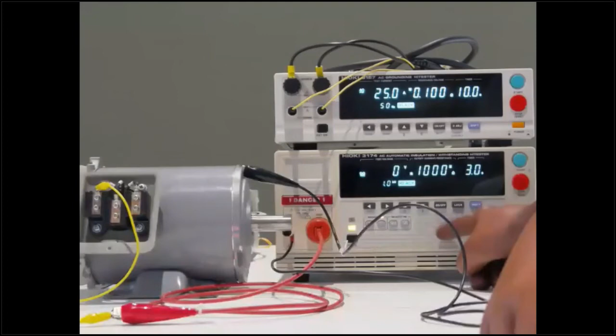In addition, the 3174 has an automatic mode, these two buttons. It's a little difficult to see, but the left button switches from W to I, and the right button switches from I to W. If you push the left button of the auto function, the 3174 will first do the withstand testing, then automatically do the insulation test.